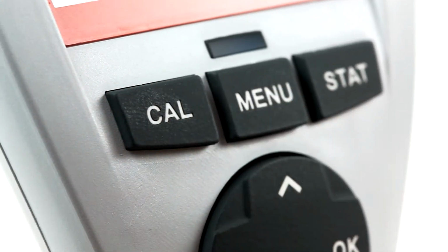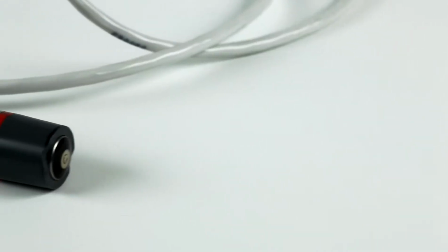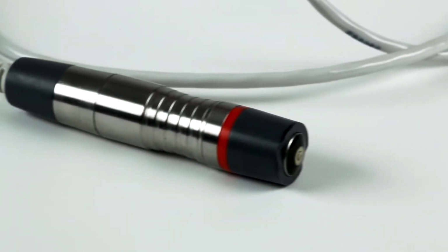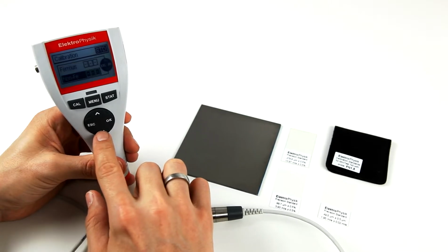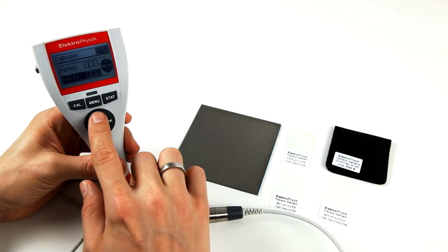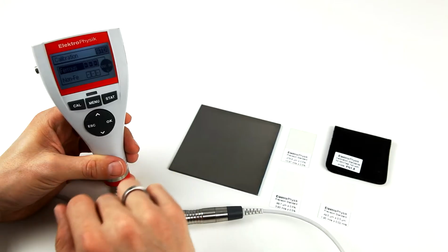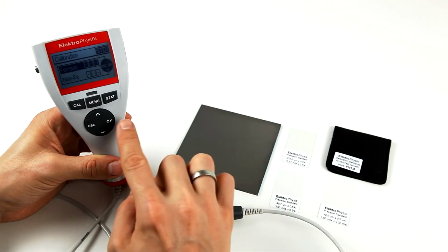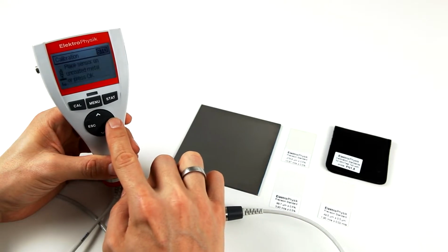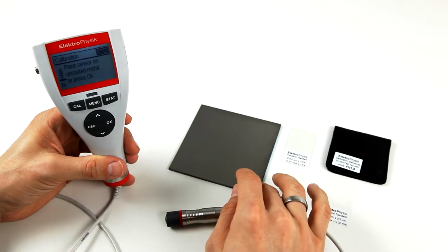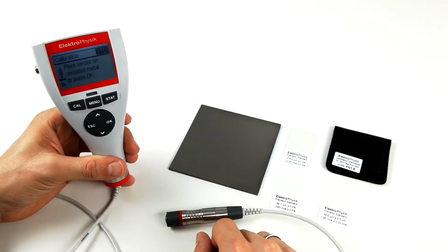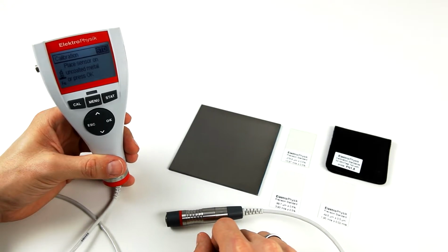To start the calibration process, press the Cal key. Once the FN sensor, which is connected to the gauge, is employed, the menu will request you to select either calibration on a magnetic or a non-magnetic substrate. We will select the magnetic substrate. Hence, we will use the steel zero plate taken from the set of calibration standards, which is applied with the sensor. In practice, it is always recommended to perform a calibration on an uncoated sample made of the same material and with the same geometry as the object to be measured.